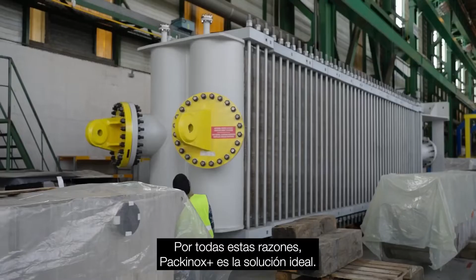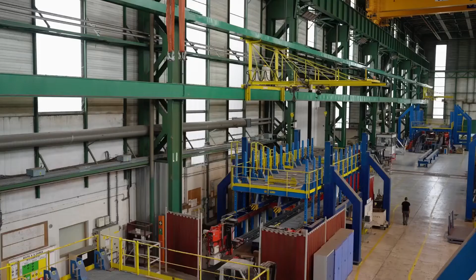It combines in the same heat exchanger high-performance corrugated channels and true countercurrent configuration, which leads to half the heat transfer area that would be required for a shell and tube solution. It makes a huge capex difference when you require tens and hundreds of thousands of square meters, and even more when the material requested is stainless steel.